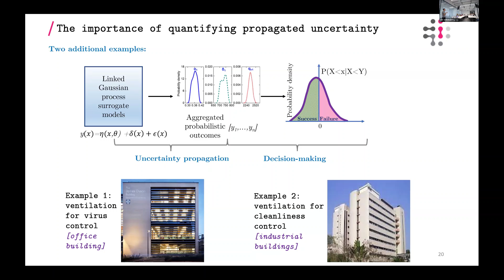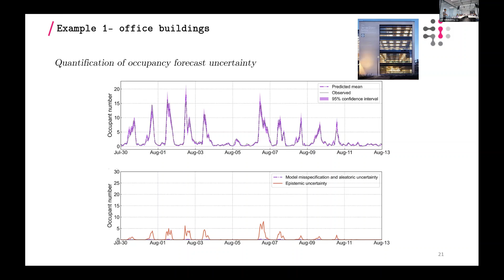For building ventilation, a key issue is identifying the occupant number inside the building, because we normally control ventilation based on how many people are inside the rooms. We use a stochastic modeling approach to quantify the occupant forecast uncertainties, shown in these slides, and quantify the different types of uncertainties. With the quantified uncertainties, we're able to propagate the occupant forecasting uncertainties into the required ventilation rates inside the buildings.